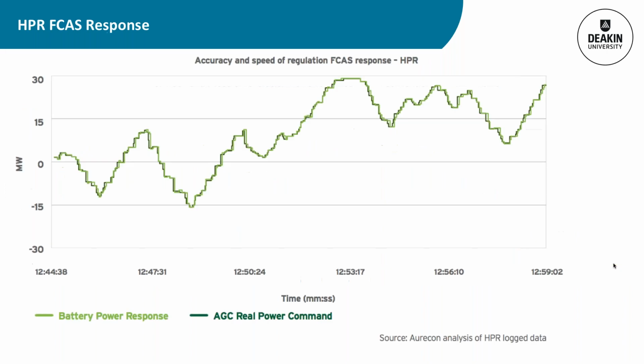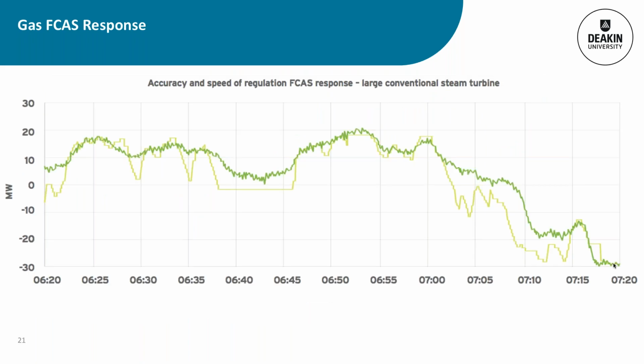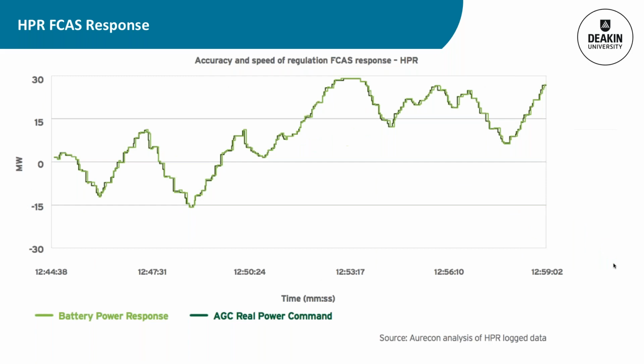If we look at what the battery did over exactly the same period, over the same hour, the power command - the signal from the grid saying how many megawatts need to be dispatched to keep the grid stable - was mirrored by the battery almost perfectly. Compared to the turbine's fairly good response, this precise response is dramatically different. But the impact of that precision isn't valued in our market at the moment.